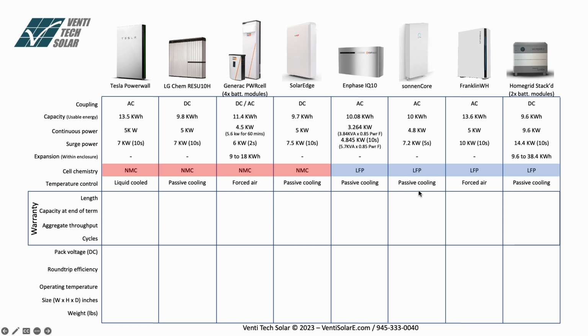Passive cooling for the Enphase, passive cooling for the SonnenCore. The Franklin chose to add forced air active cooling to their system that probably lengthened the life expectancy of the cell. It probably makes it a better system, although it probably adds complexity, adds components to the solution. And passive cooling on the home grid for LFP is perfectly acceptable. So Tesla will get the smiley face for the liquid cooling on NMC technology, and Franklin will get the smiley face for the LFP forced air cooling, active cooling on their system.